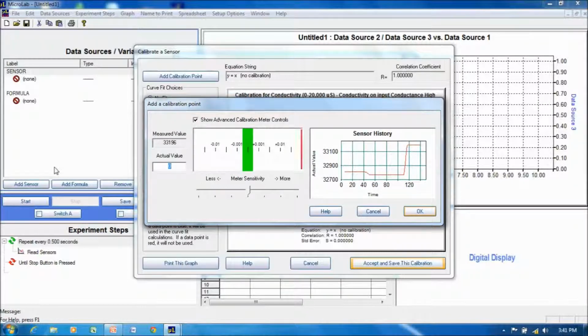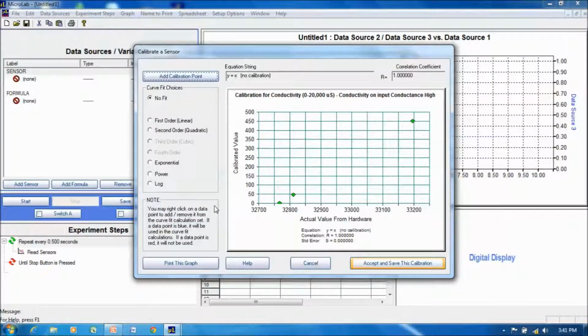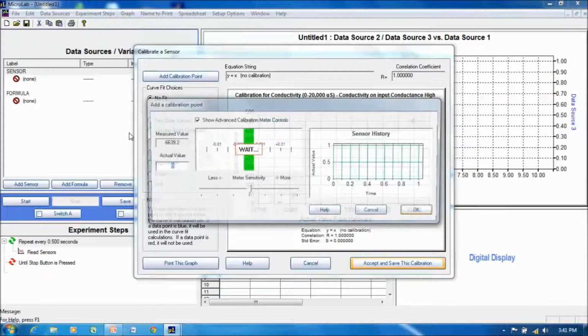Check for bubbles, no bubbles. 450. Again, we'll lower the sensitivity. Now it seems like it's kind of wildly fluctuating, but actually the measured value in random arbitrary units is 33,000 plus or minus 10. So that is actually rock stable. We'll accept that. We're going to add another calibration point.